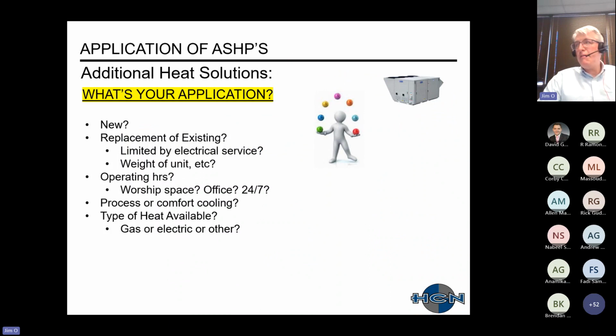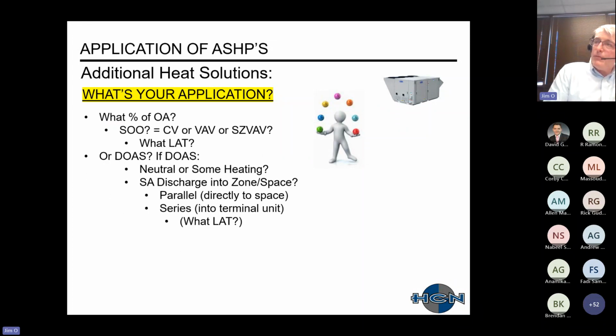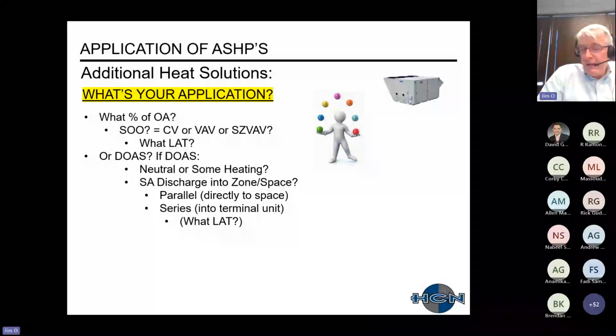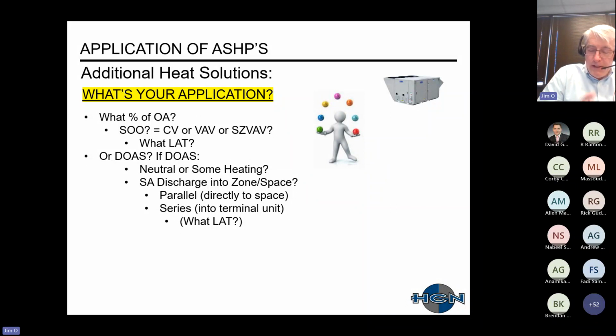So back to what's your application? Do you have a new system that you're designing? Is it a replacement of existing? Are you limited by electrical service? What's the weight of the existing unit versus new? What are your operating hours for those radically different spaces? Is it process or comfort cooling? And then also, what type of auxiliary heat do you have available? Other items about your application: what's your percentage of outside air? What would be your sequence of operation? What leaving air temperature are you looking for? And then also, associated with the DOAS system, essentially what's your leaving air temperature that you're going to be considering with those different options there.